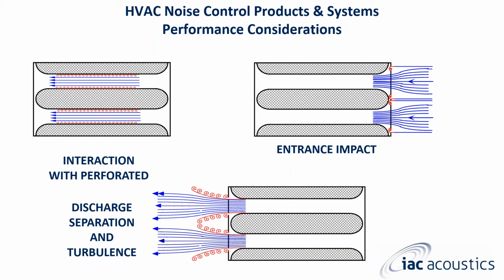Now, at the top left, you can see some self noise can be caused by the interaction with the perforated material within the silencer. Typically, you're going to hear some self noise if this is installed right up against the fan or the piece of equipment. With a higher rated pressure system, say 10, 12, 20, 30, 40,000 CFM, you're flowing air out of 100% area, say 40 by 40, directly into a silencer that could be 40% free open area. That could cause some whistling effect.